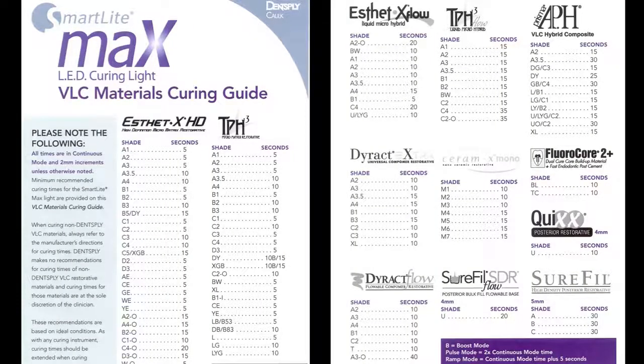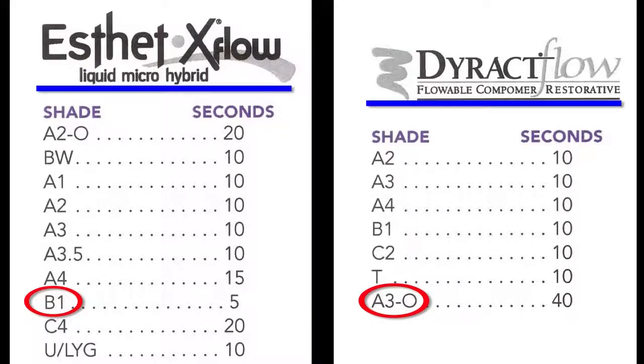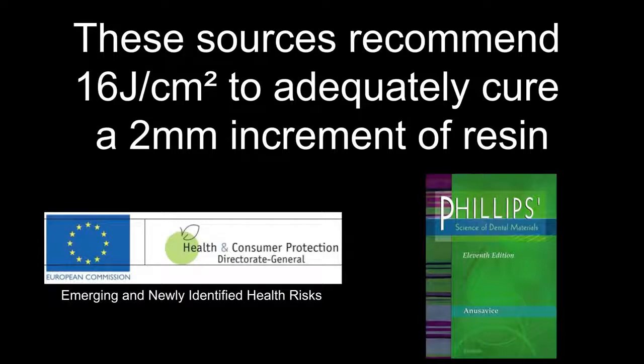Instructions with the SmartLite Max curing light recommend use from anywhere between 5 and 40 seconds depending on the shade and type of resin. According to Dentsply, this light delivers 1200 mW per centimeter squared, meaning dentists must deliver between 6 and 48 joules per centimeter squared. Alternative sources such as the Phillips textbook and the European Commission on Emerging and Newly Identified Health Risks both recommend delivering 16 joules per centimeter squared to adequately cure a 2 mm increment of resin, though this depends on shade and resin type.